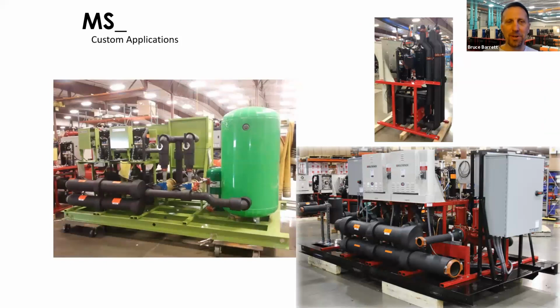Custom applications. The green isn't very pretty, but the school wanted it painted their colors. Apparently they're lime green. That's about as close as we could get in PVC colors. It's a little bit different, but really shows off what we can do. This happened to be a primary-secondary system, all pre-engineered on a skid right down to the buffer tank. Painted all of the steel components green, fully insulated. Put the skid on a truck, drive it down, put it in the mechanical room, connect your piping, connect power, and do the startup, and you're off.